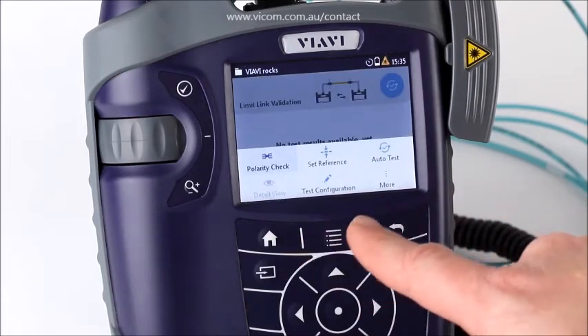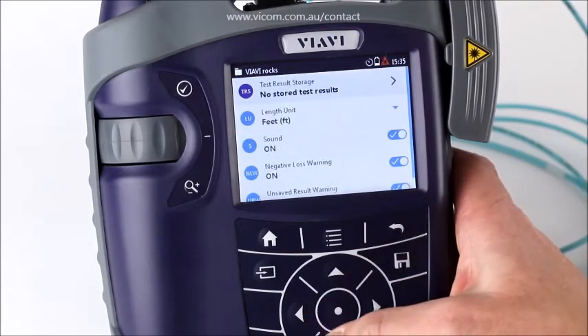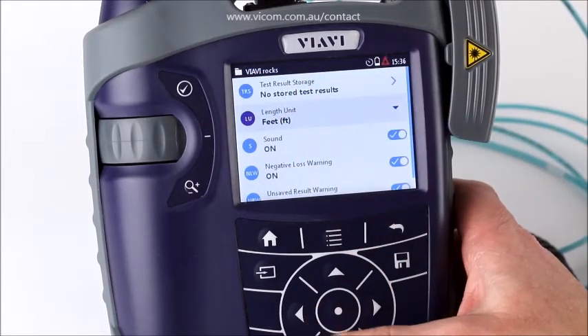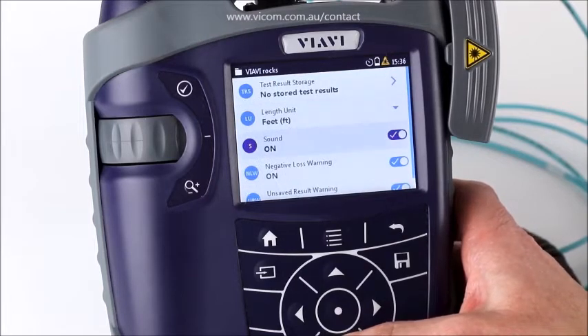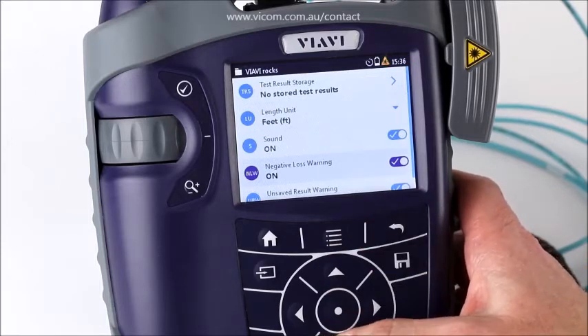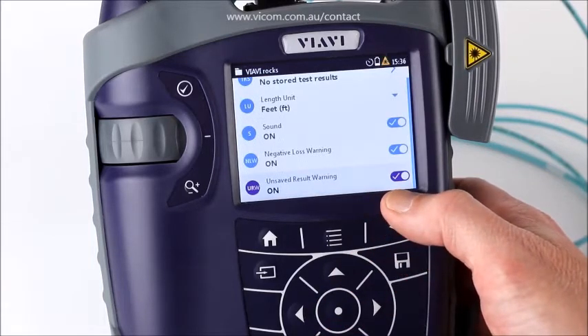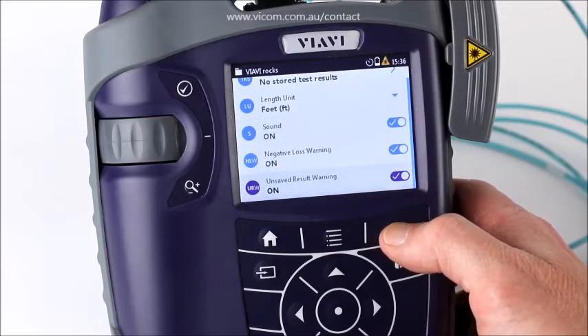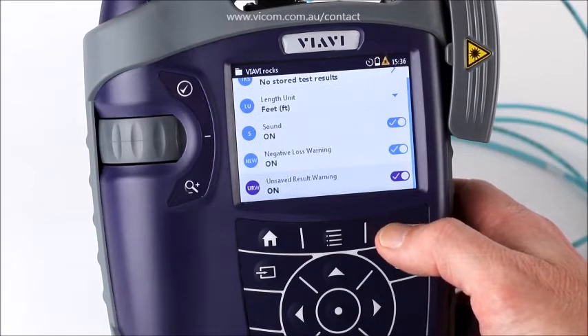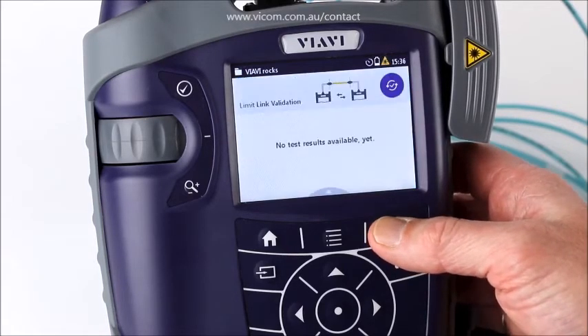The More button gives you some additional options. At the top you can view test results stored for that project. You can change whether all your tests measure in feet or meters. You can turn sound on or off — when connectors connect together it makes a noise. You can also toggle a negative loss warning on or off; by default it's on and we recommend leaving it that way. There is also an unsaved result warning — if you need to save results, leave this on, as it prevents you from exiting the results screen without saving. If you're just testing and don't care about saving, turn that off so you're not annoyed by save prompts.